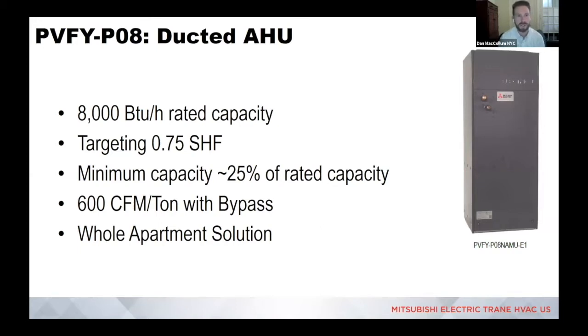Usually VRF systems live around the 0.8 sensible heat factor ratio neighborhood. So a 0.75 sensible heat factor ratio is an improvement. And what that does is it gives you more latent capacity for the moisture removal that we see as being critical in passive house projects. The unit was designed at 600 CFM per ton, which is a pretty high CFM per ton value. And part of the reason that decision was made was because this unit was designed with a whole apartment solution in mind. So this unit wasn't designed to really be a single zone space.